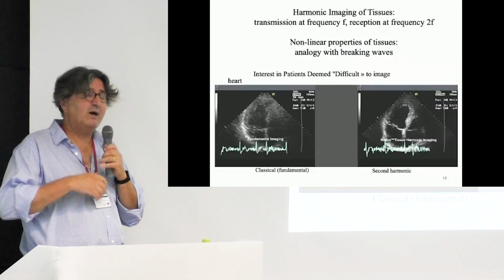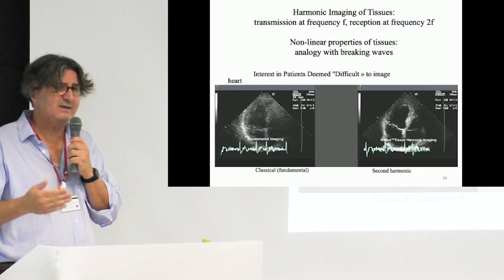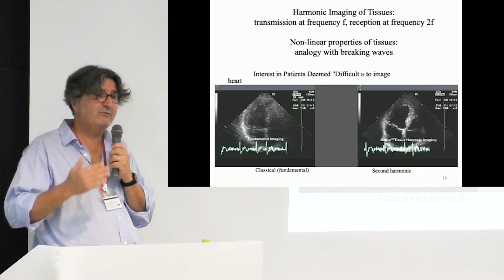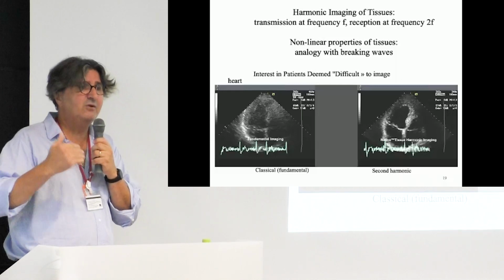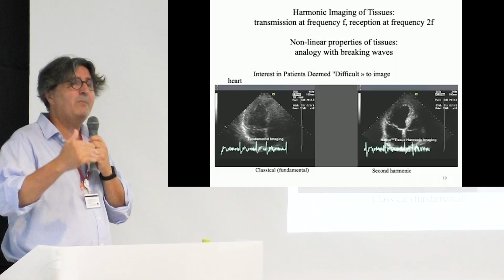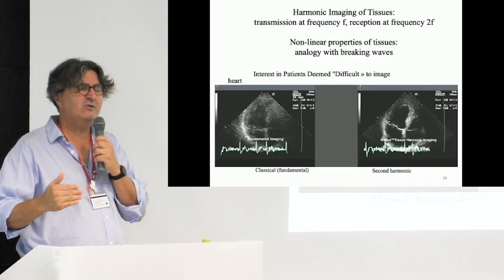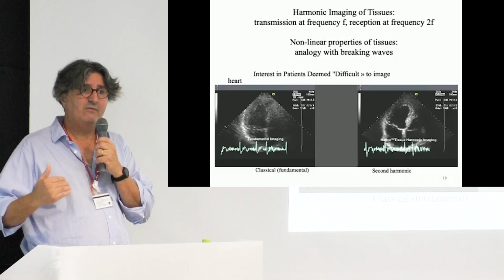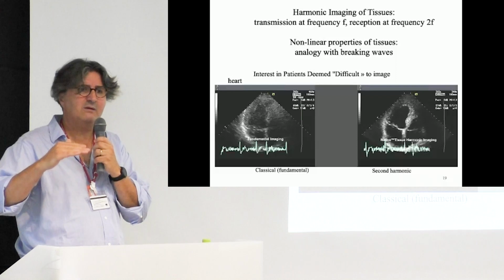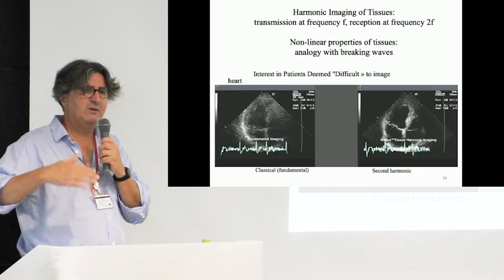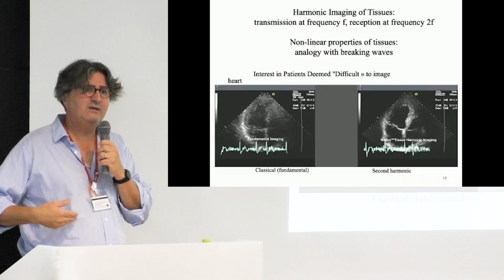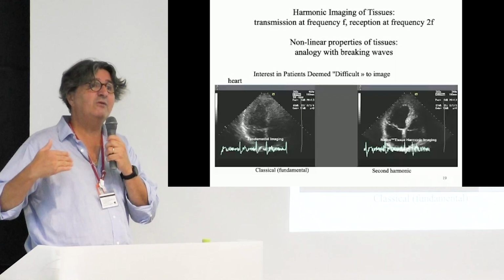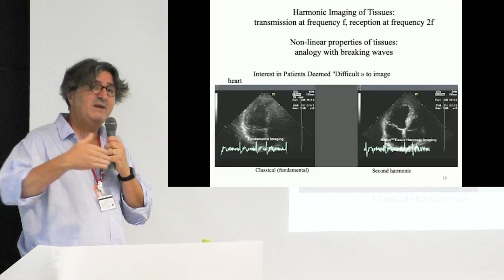And when you are doing second harmonic analysis, you have to remember that the second harmonic effect, the nonlinear effect that you have during the propagation of the ultrasonic wave, depends on the power level, but we are limited on the power level, of course, because we don't want to heat the tissues in the body, and it depends on the penetration depth.